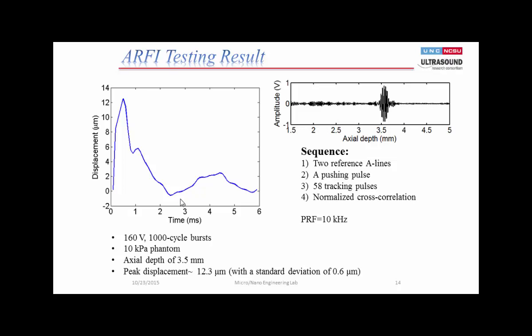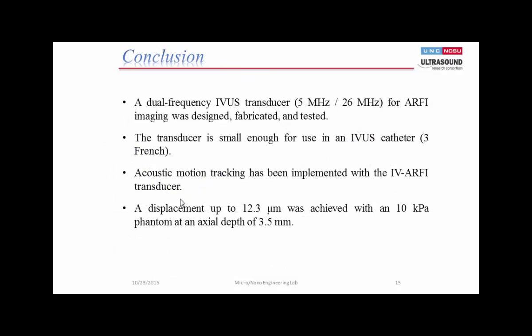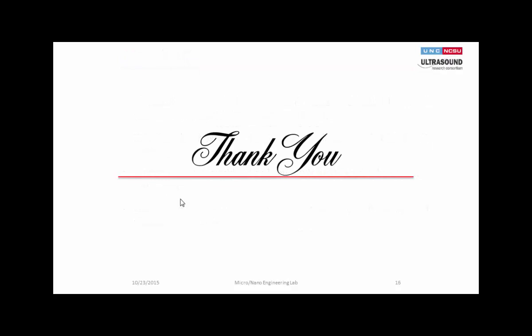The next step is something similar to what Dr. Ma already presented — we'll do a lot more B-mode imaging, and ex vivo and in vivo studies with the dual-frequency transducer. In conclusion, we were able to apply the dual-frequency IVUS transducer for ARFI testing. The pushing transducer was able to push the tissue phantom, and the tracking transducer detected a displacement of about 12 microns with the 10 kPa phantom. That's something we're happy to see as an initial test. With that, we'll stop here. Thank you.